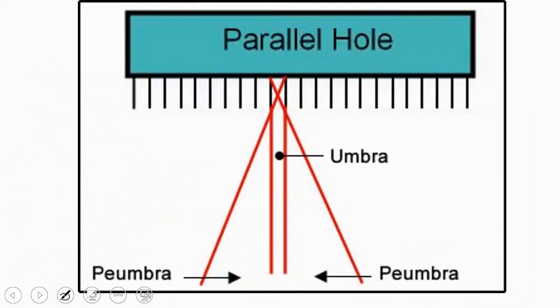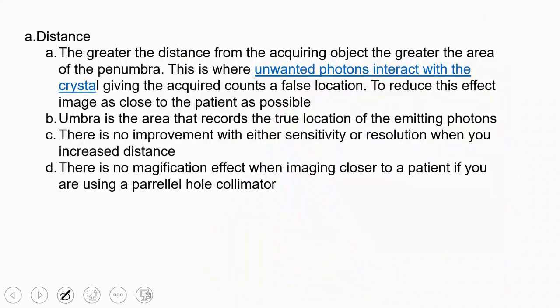This is similar to our discussion about the X-ray tube here. The idea is that the farther you are from the detector, the scattered angle or scattered photon coming from your margins will weaken the resolution of your object, thus increasing the penumbra region. If you are closer, the likelihood of the scattered photon passing through these holes and being detected increases. So, distance is a parameter affecting sensitivity and resolution.